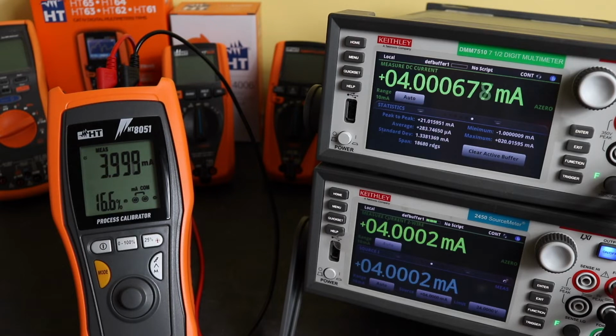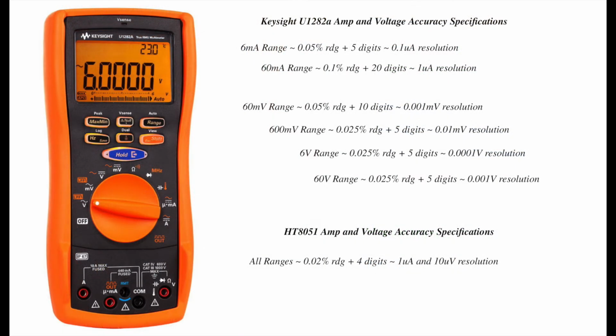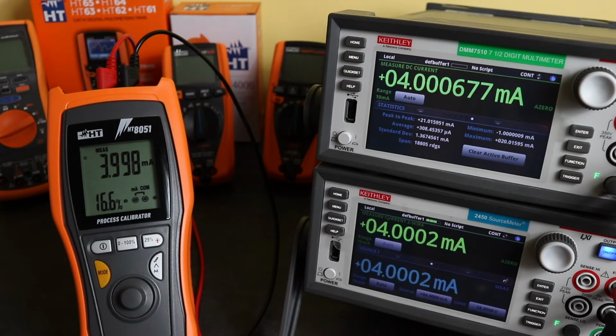As a comparison, the U1282A multimeter I have from Keysight, on its 6 milliamp range, that can do 0.05% plus 5 digits. On the 60 milliamp range, that is 0.1% plus 20 digits. So quite a bit less accurate than the HT8051. In terms of voltage, up to 10 volts I would have to go up to the 60 volt range, so that would be 0.025% plus 5 digits. But it also does that in the 6 volt range as well, and the 600 millivolt range. So you could use that in place of this for the voltage function, but you couldn't use it to check out the functionality of this.